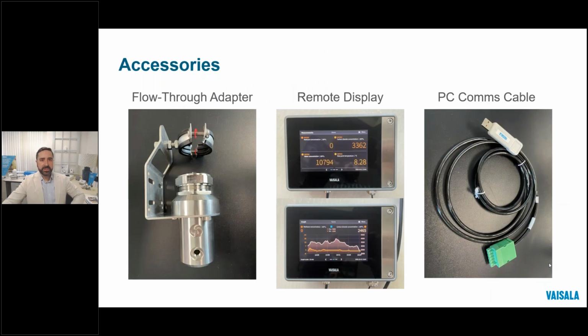And despite having no sampling systems, we do have a couple of accessories available, such as a graphical display with data logger and multiple other communication options. We also have a flow-through adapter. This does allow you to mount the probes remotely if you'd like, and it's just a simple stainless sample cell with an inlet and an outlet. This can be used for field calibration or adjustment, with our USB service cable and free Insight PC software as the interface. Next, please.